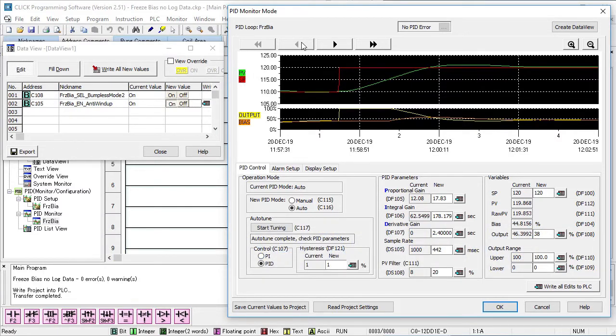By the way, this is also why getting your sample time right is important. If you have a sample time that's real long, then you get a crude approximation of the area. If you have a really short sample time, then you get a super accurate estimate of the area, but you just unnecessarily wasted a bunch of processor time. So you want a sample time that's good enough.